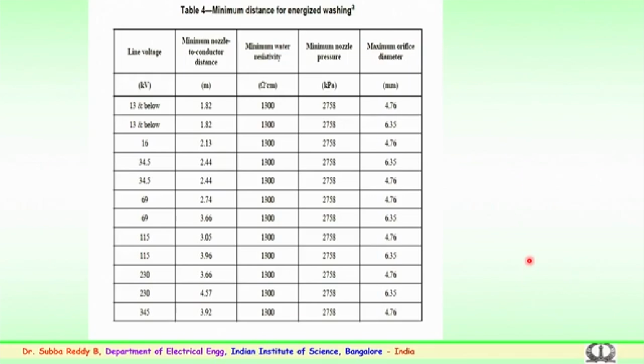This gives some information about the minimum distances for energized washing. So, this is again available in the standards which I mentioned for cleaning of insulators. To show you a typical example, considering some voltage levels, say 33 or 35 kV, 34.5 is the line voltage. In such cases the minimum nozzle to conductor distance mentioned is 2.4 meters. So, a person or whatever the arrangements, the nozzle sets have to be at a distance of 2.4 meters, and the minimum resistivity of water is mentioned to be 1300 ohm centimeter, and the minimum pressure is 2758 kilopascals, and the maximum orifice diameter is mentioned as 6.35 millimeters. So, this is a typical example which I have cited.